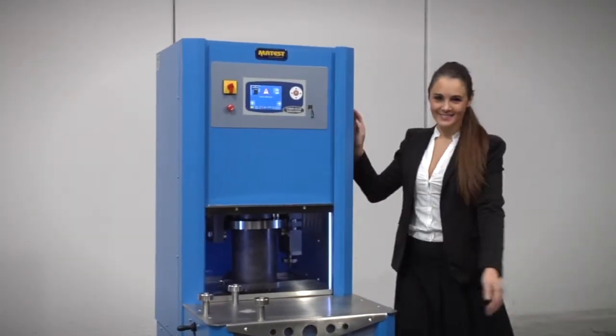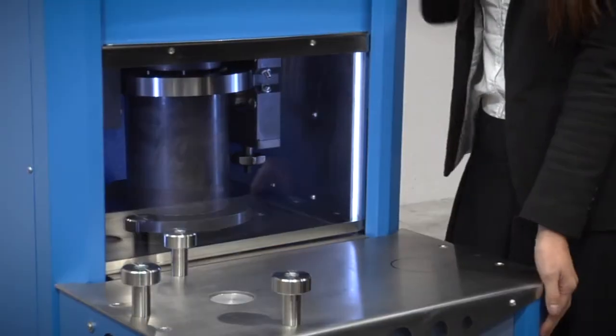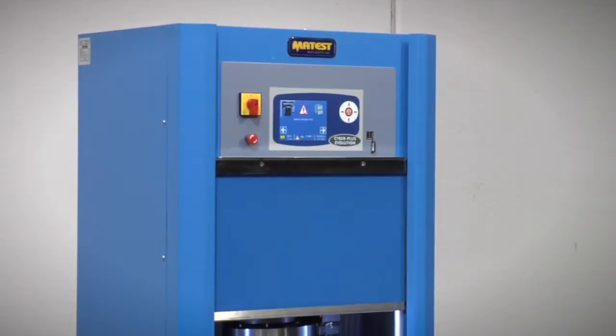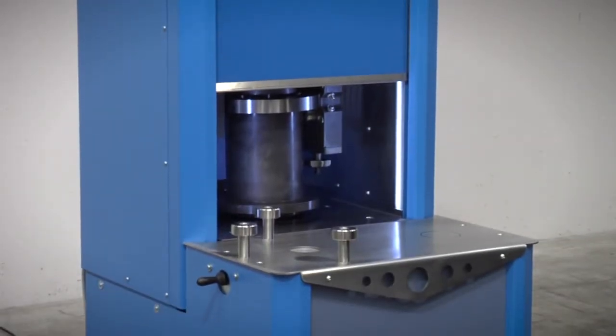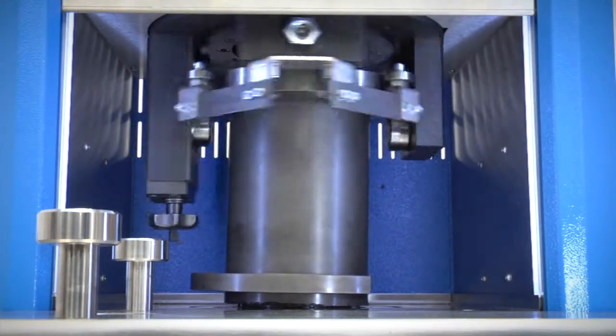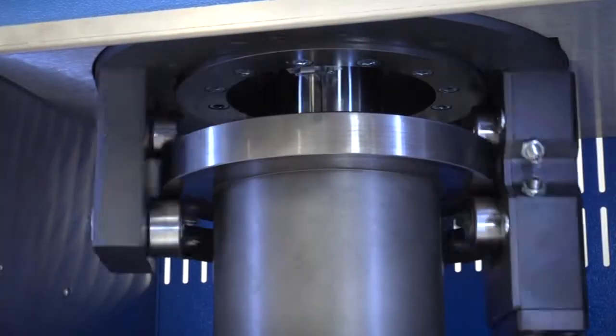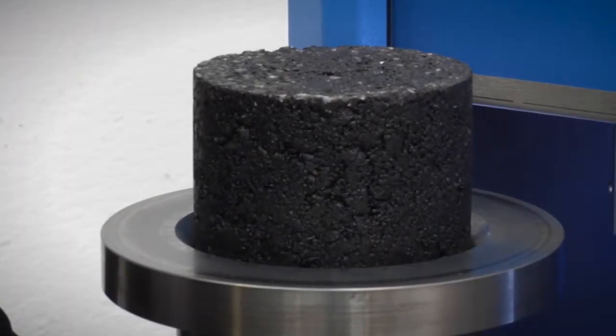The MaTest Gyratory Compactor is designed and manufactured with the latest technologies in accordance with the SuperPave system, and complies with ASTM, AASHTO and EN standards. It has been developed for the SuperPave asphalt mixture design to avoid premature deterioration of asphalt pavements. The machine is used to simulate real compaction conditions under actual road paving operations to determine the density and compactability of hot mix asphalt, and to prepare cylindrical specimens for Marshall and AMPT tests.